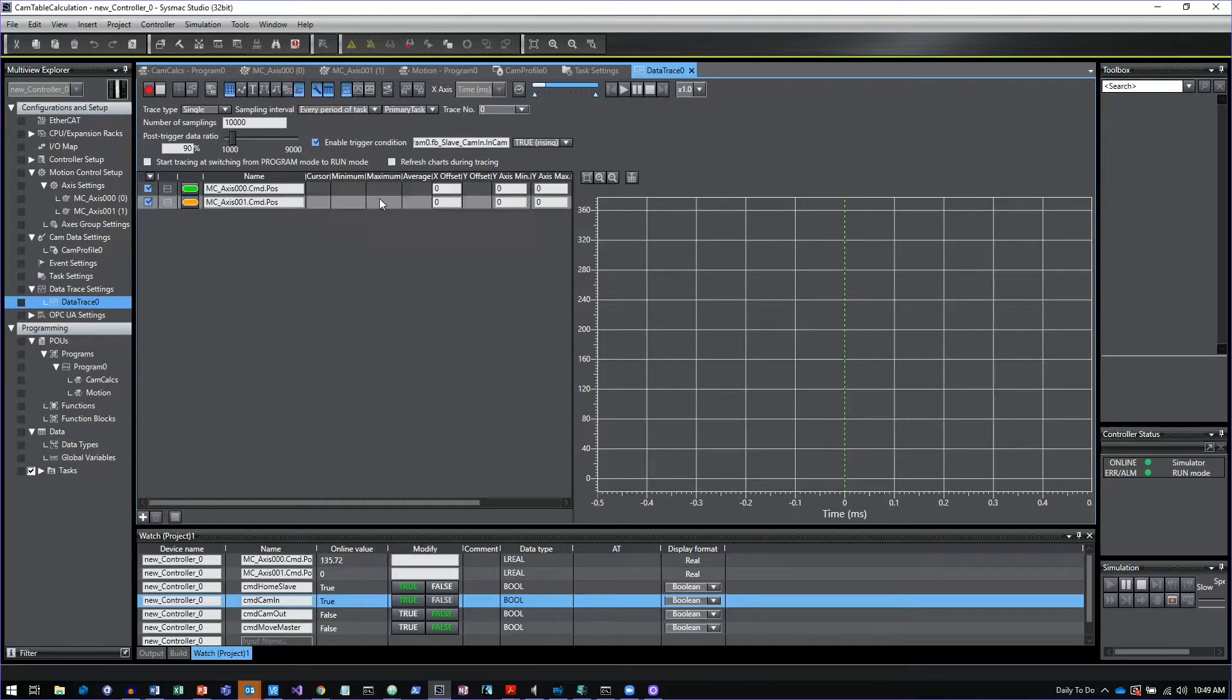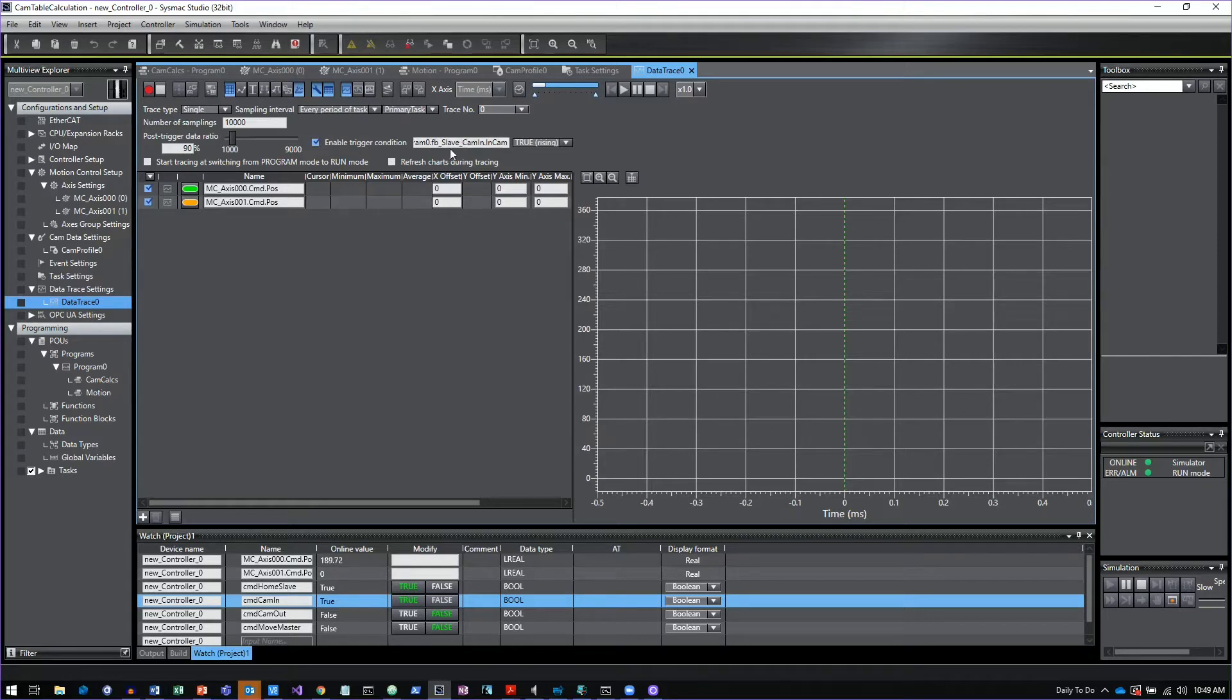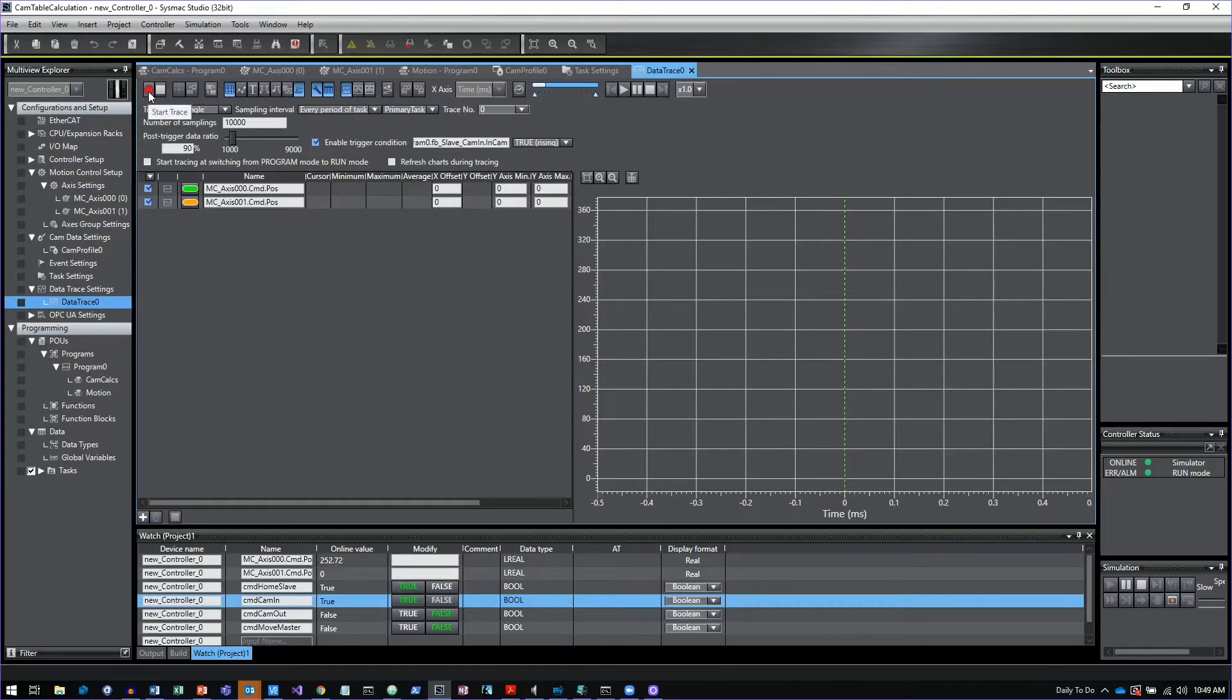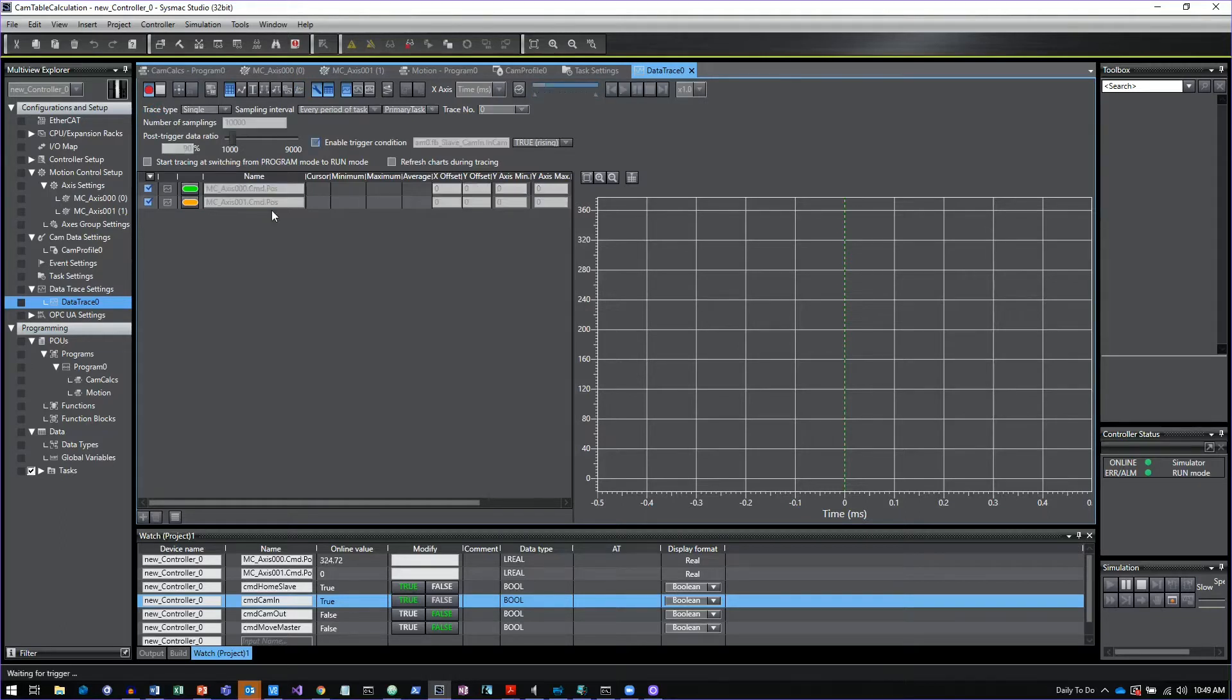The other thing I did is I've got this in an enable trigger condition. What I'm looking at is I have a function block for my cam in and I'm just going to look at the in cam status bit of when that goes to true and use that as my trigger. Click start trace and that basically arms the trace now waiting for the trigger event.